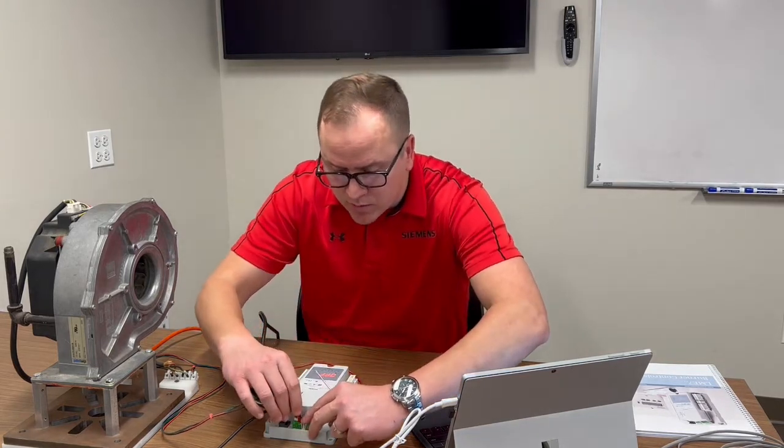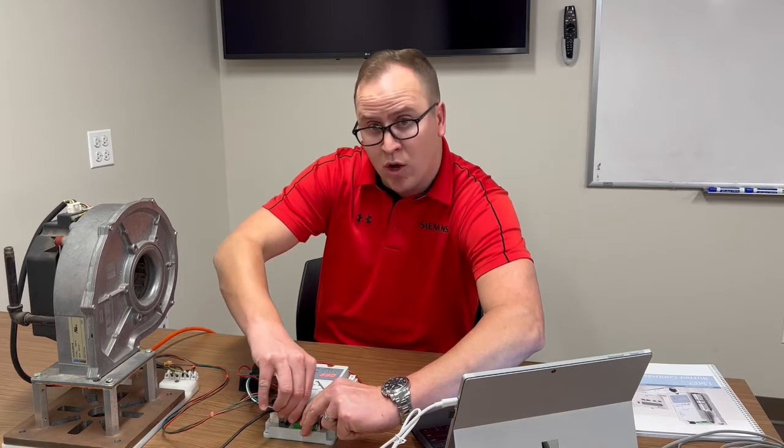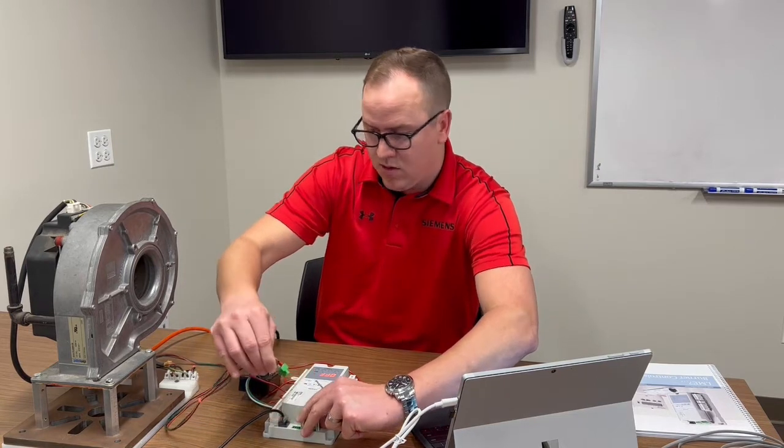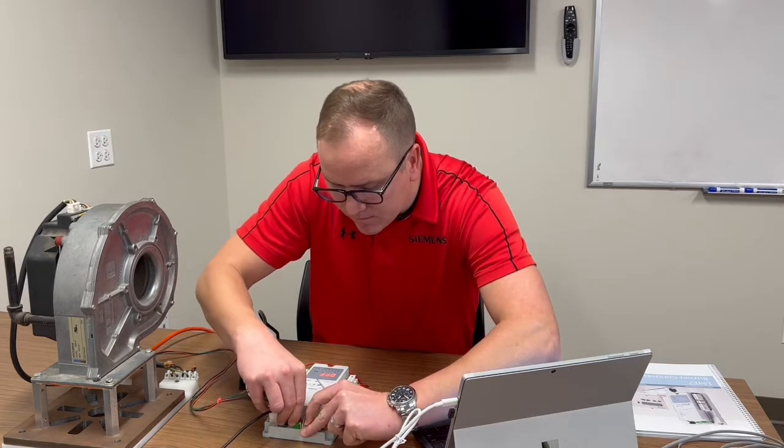If I take the PWM signal, these are the wires here. If I remove it, the blower is going to go to high speed. You plug it back in, the PWM signal essentially applies the brakes and is now in control.